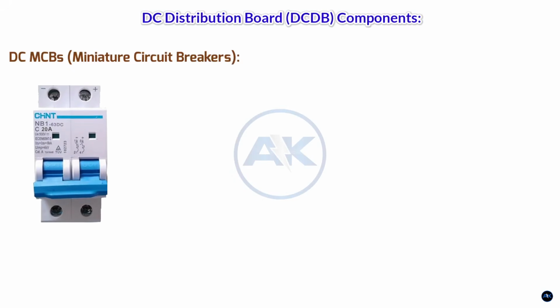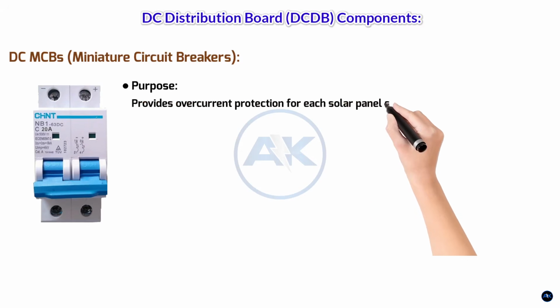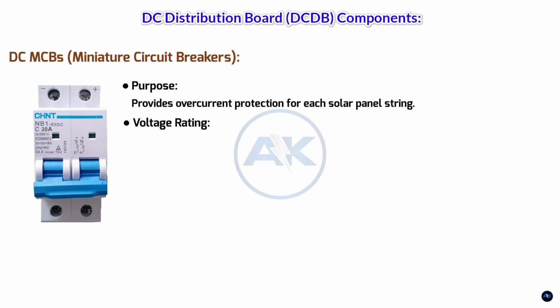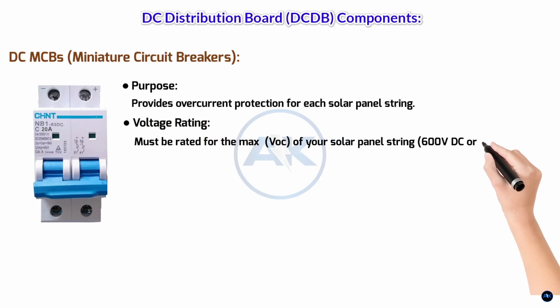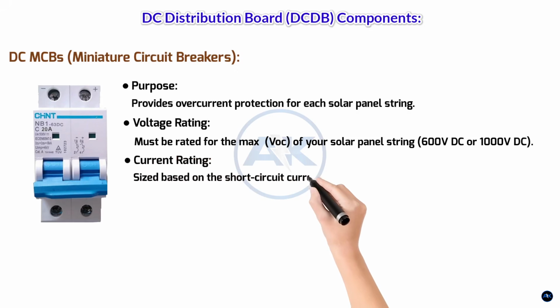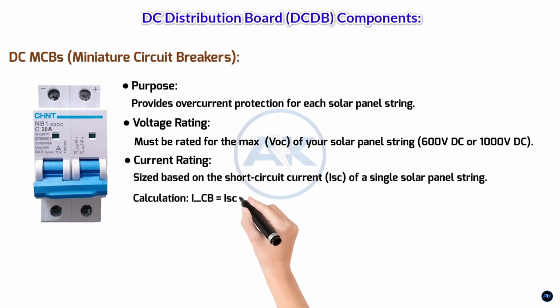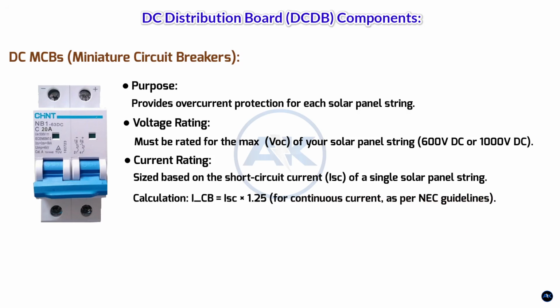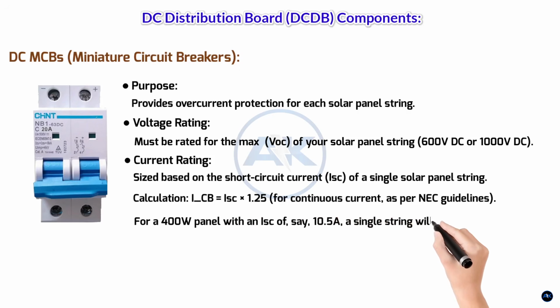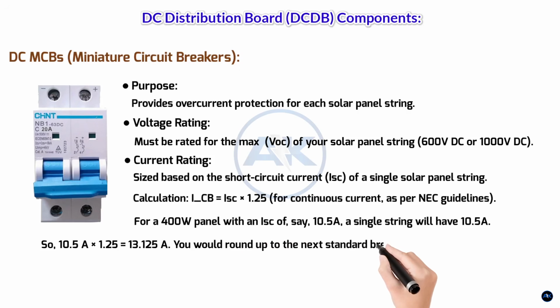DC MCBs, miniature circuit breakers. Purpose: provides overcurrent protection for each solar panel string, allowing for isolation of individual strings for troubleshooting or maintenance. Voltage rating: must be rated for the maximum open circuit voltage, VOC, of your solar panel string, 600 volts DC or 1000 volts DC. Current rating: sized based on the short circuit current, ISC, of a single solar panel string. Calculation: I_CB equals ISC string multiplied by 1.25 for continuous current as per NEC guidelines. For a 400 watt panel with an ISC of say 10.5 amps, a single string will have 10.5 amps. So 10.5 amps multiplied by 1.25 equals 13.125 amps. You would round up to the next standard breaker size, typically 15A or 20A DC.